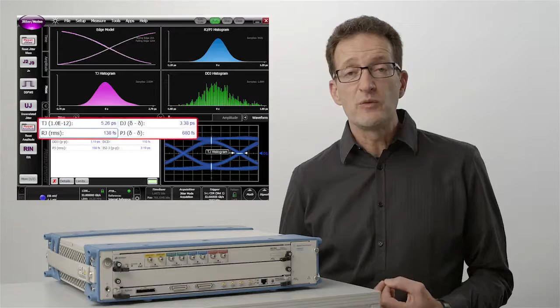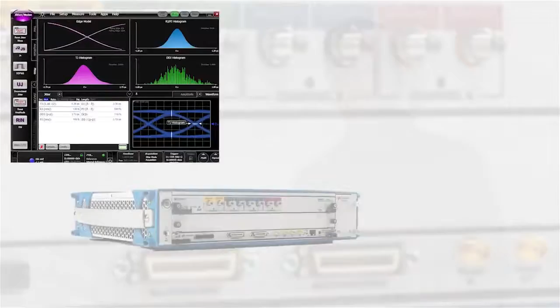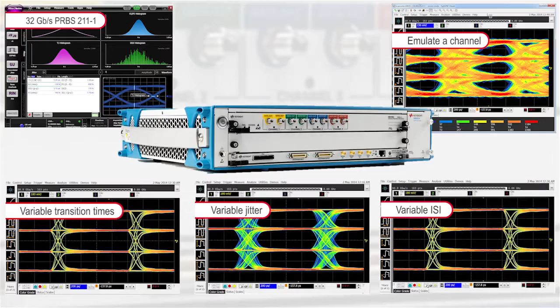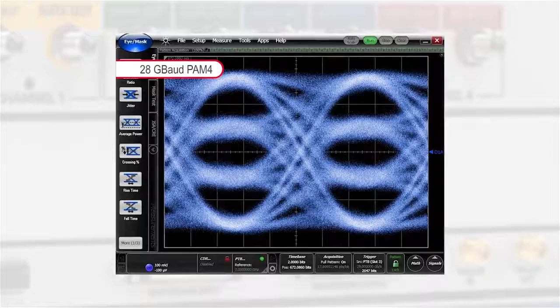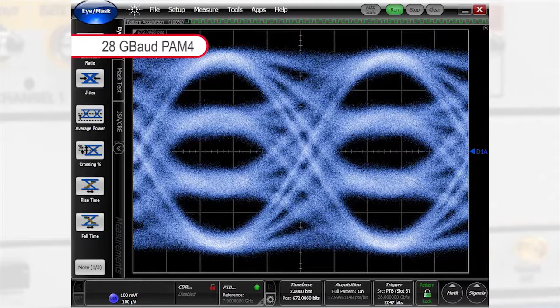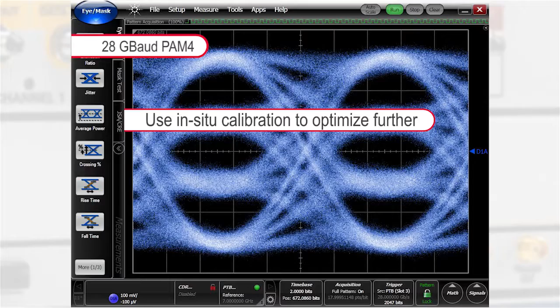For testing digital and multi-level interfaces, such as PAM4, at data rates up to 32 gigabaud, the M8195A provides very low intrinsic jitter and allows you to vary parameters such as transition times, noise, jitter, and intersymbol interference without additional hardware. On top of that, embedding and de-embedding of S parameters can be used to emulate a worst-case channel. With built-in frequency and phase response calibration, the AWG generates a clean signal right out of the box, even at highest data rates. Additional in situ calibration can be used to further optimize the signal at the desired test point.